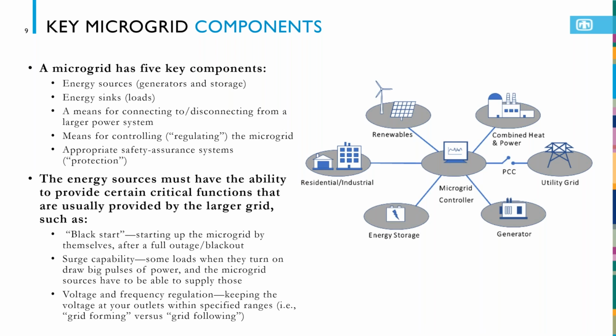And then, of course, the voltage and frequency regulation is big. The loads, residential loads, industrial loads, require 60 hertz. Internationally, it's 50 hertz, cycles per second. And you have to make sure that you keep within those frequency ranges. Anytime there's perturbation from renewables, which are a variable source, it can perturb the system in such a way that you don't want that frequency to become so low or so high, and some of these loads can be very susceptible to that. So you have to be very careful on how you do frequency and voltage regulation.